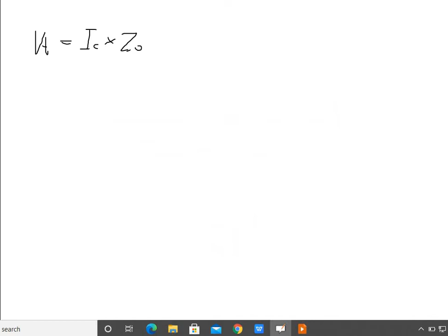So current chopping is mainly observed in vacuum circuit breakers or in the case of air blast circuit breakers. And there is no current chopping phenomenon in the case of oil circuit breakers. So why, that I will tell you at the end of this video. Current chopping is predominant while switching a shunt reactor or unloaded transformer, meaning when we are going to interrupt the magnetizing current, the current chopping phenomenon can be observed.